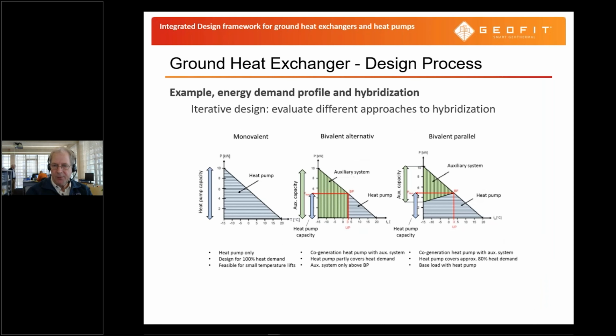So one example, and we go a little bit more into detail when we start talking about the heat pump system, is how are we going to deal with the total energy demand profile that we have. So this is about the hybridization, which often in retrofit case we will have, that we... so what we want to do here is, for instance, take a look at how much of the total energy are we going to cover by the heat pump, and how much of the total energy are we going to cover with the auxiliary system, like a gas-fired boiler or other systems that are in place. And what we can see here, let me put my pointer to laser.